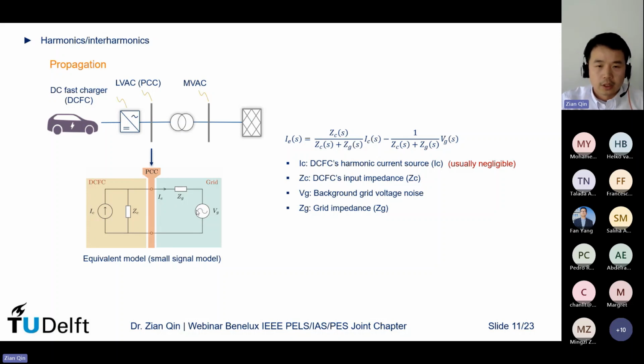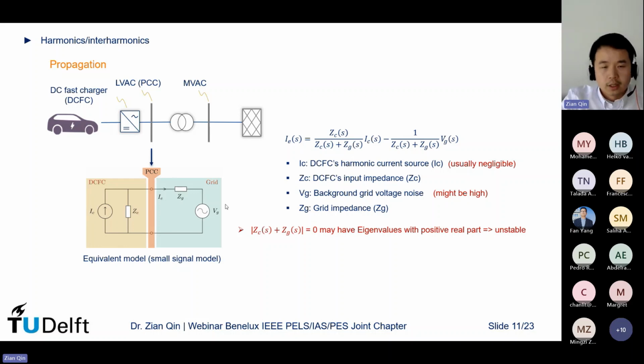Then the background noise. The grid operator will make sure the background noise is in an acceptable range, right? So it might be high, but still be in an acceptable range, I would say. But eventually, you may still have the problem. Then I would say it's mainly because of the mismatch between these 2 impedances. If you look at this equation, here I show the harmonic current at the PCC point. If you calculate the harmonic voltage at the PCC point, you will get a similar equation, which means the denominator will be the same. So if the denominator has an eigenvalue with a positive real part, then this grid connection will become unstable.